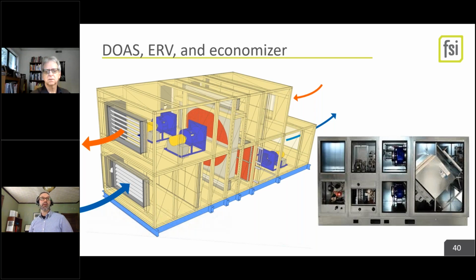And those can be built up, and those can be the size of a bus, essentially, an extraordinarily large thing that goes on. It's not necessarily always a rectangle. They will bend corners and things. But those more modest size units will come in on a crane in one lift. And yep. Those giant ones you're talking about would come in several chunks and get hooked together? Correct. And if we're saying some office buildings we're doing, this just looks like another air handler. They can come down to tiny form factors. They make residential scale ones that are the size of a briefcase. So basically any scale you need can be done with DOAS.